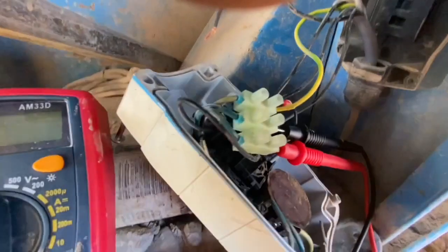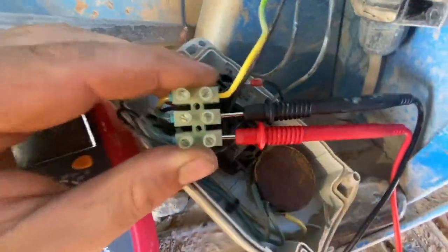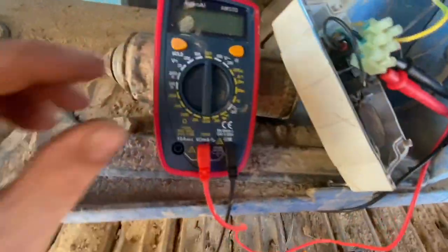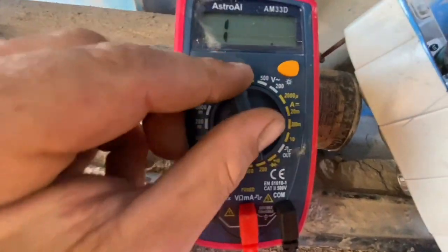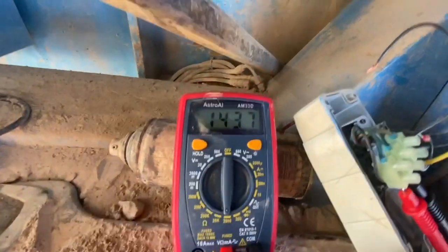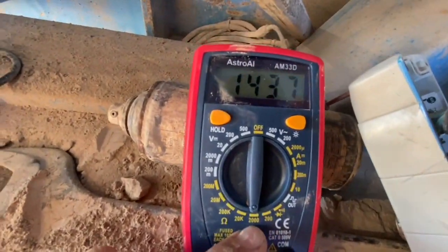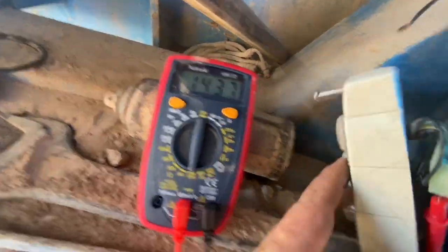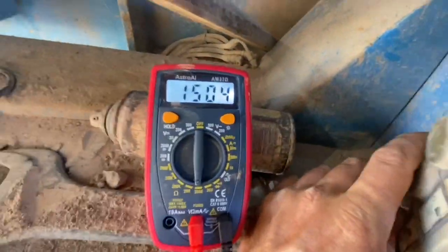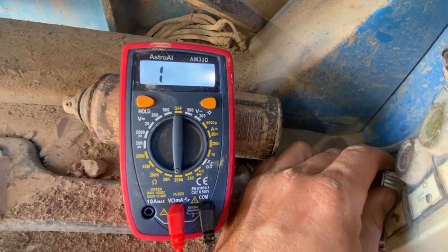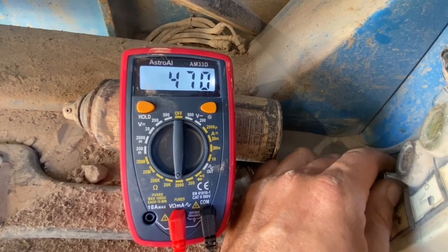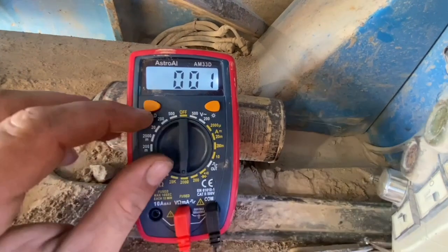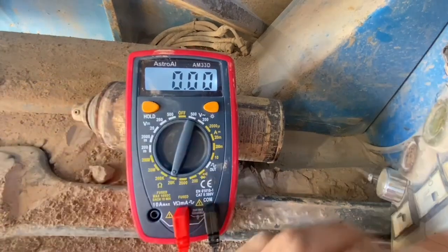So this is a potentiometer on a machine. It's a 2,000 ohm potentiometer, so it goes from zero to 2,000 ohms resistance. So we've screwed our multimeter in, we've plugged it in, and now we're just going to have a look at the reading. We've got 1,400 there. Just wind it up and down. It looks like this potentiometer might be going just over 2,000 ohms resistance. Goes all the way down to zero. That's perfect.